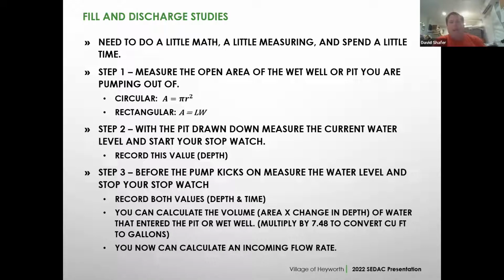If you're a rectangular pit, then you're just length times width. And I like to start with the pit mostly drawn down or pumped down. I'm going to measure the current water level and start a stopwatch. Usually I measure from a defined point at the top of the wet well down to the surface of the water. I'll record, hey, that was 12 feet, start my watch, and kick back for a little bit.